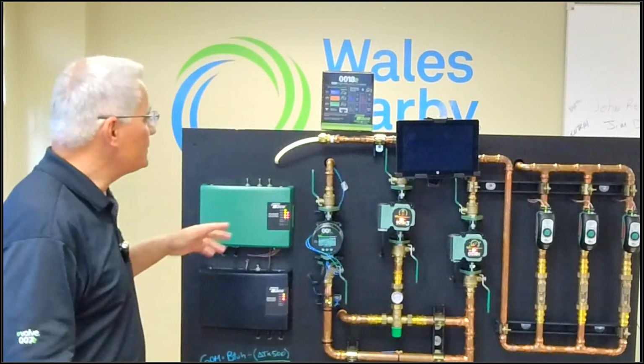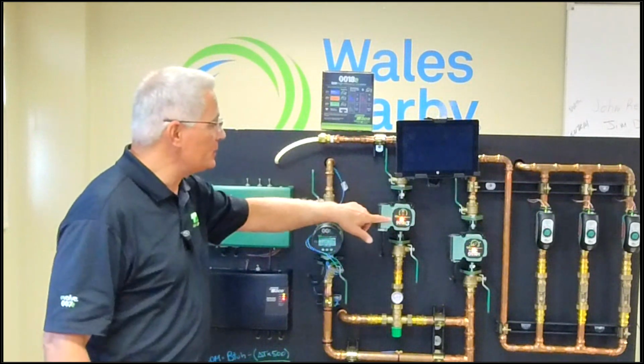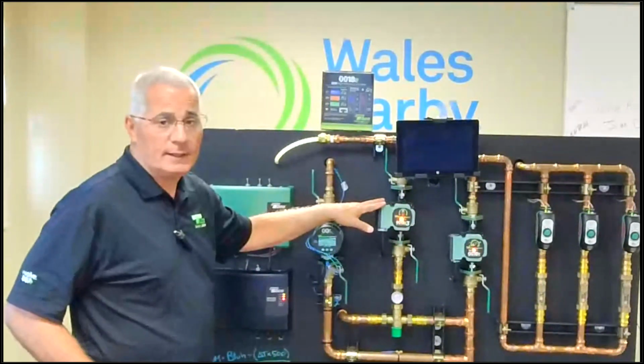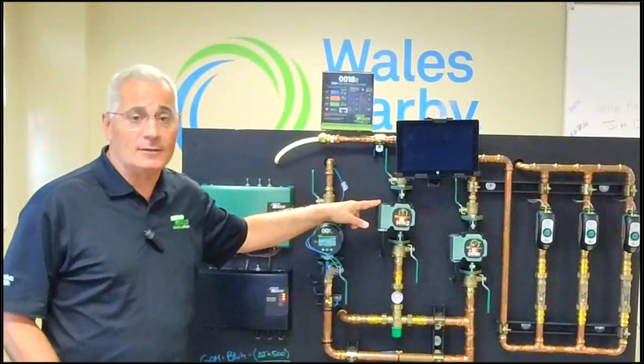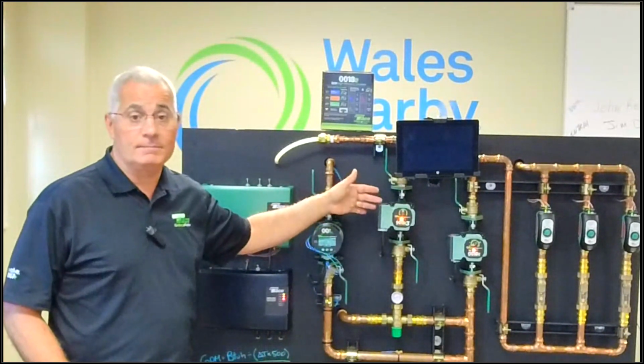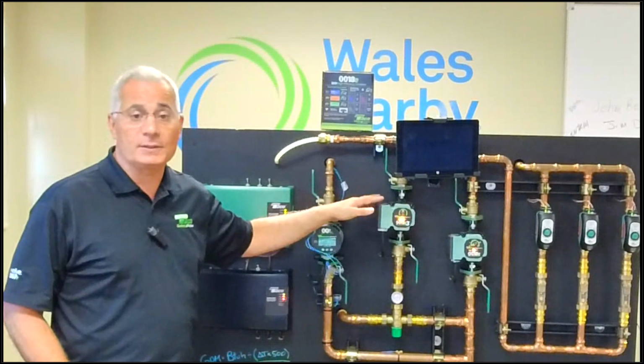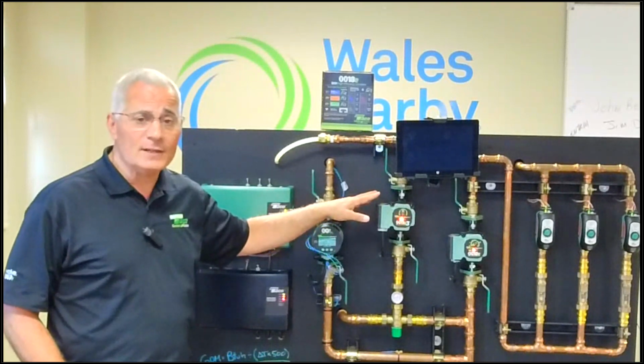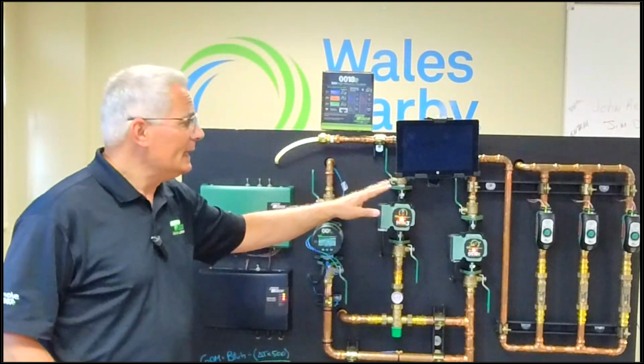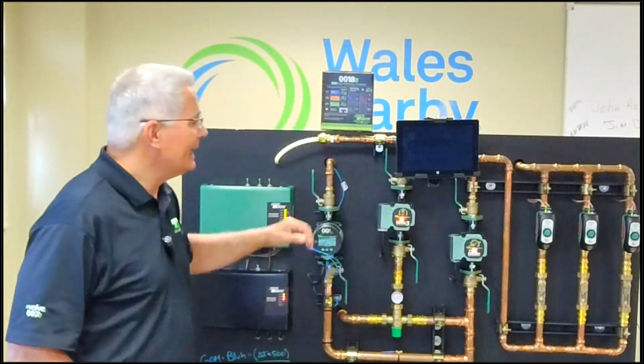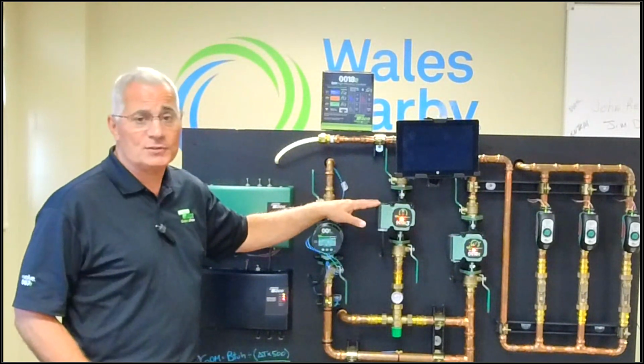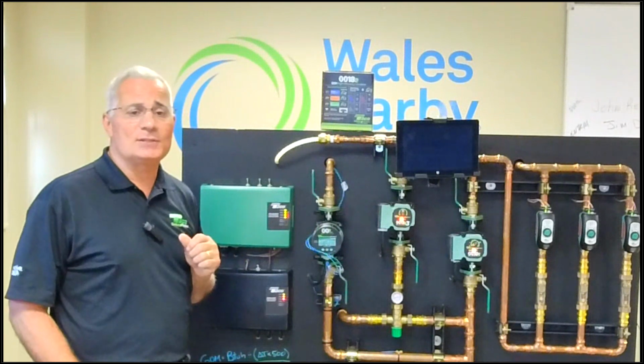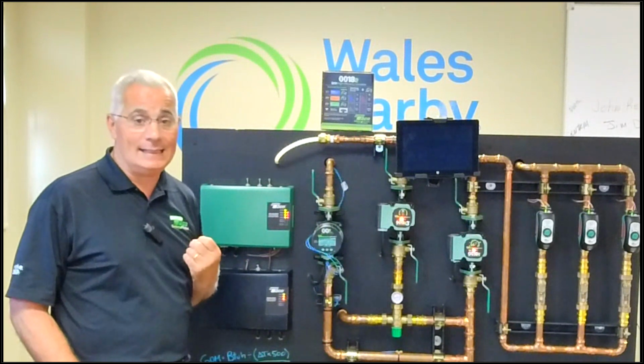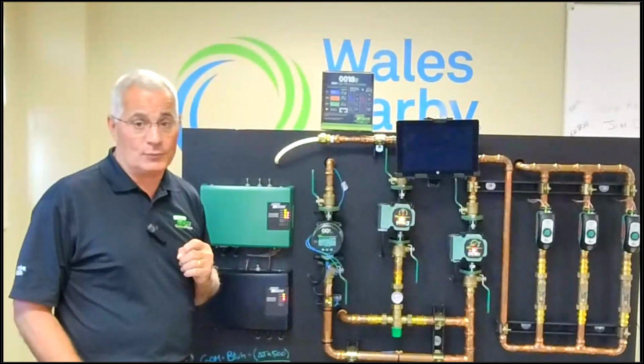Okay, all right, so that's the radiant side of the equation. So using this circulator on a lot of radiant jobs, which I happen to spec a lot, this is the circulator of choice. And if I was zoning with circulators, even on the space heating side, this is my circulator of choice because I can get as close as the GPM and head that I need at an economical price.